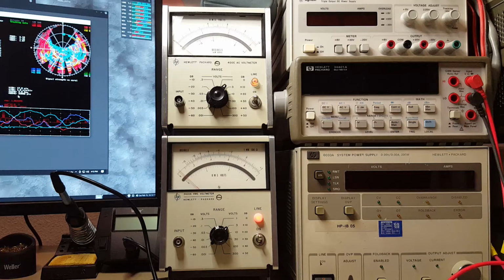Now, the top one is pretty much good for just sinusoids only. If you try to measure any other waveform, it will introduce measurement errors that will have to be corrected. The bottom one, on the other hand, doesn't care what the waveform shape is.